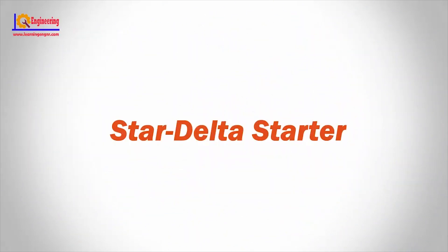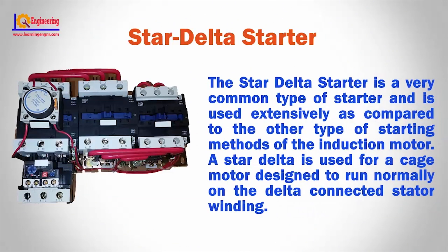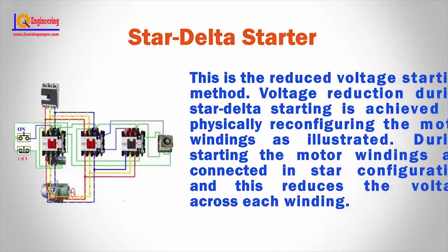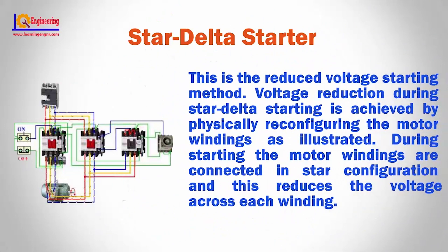Star delta starter. The star delta starter is a very common type of starter and is used extensively compared to other starting methods of the induction motor. A star delta starter is used for a cage motor designed to run normally on the delta connected stator winding. This is the reduced voltage starting method. Voltage reduction during star delta starting is achieved by physically reconfiguring the motor windings as illustrated.